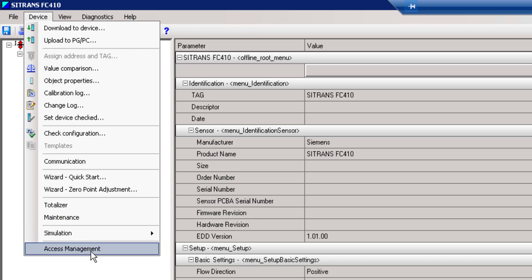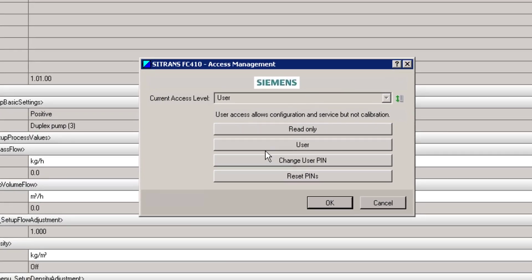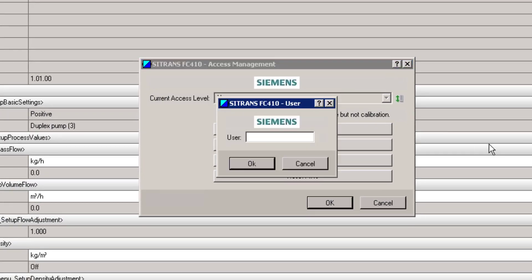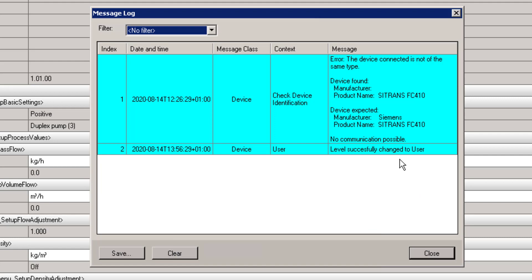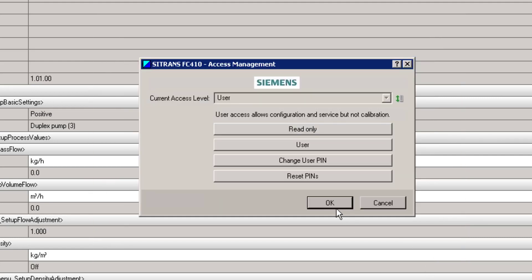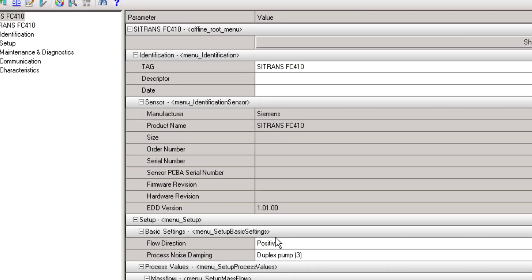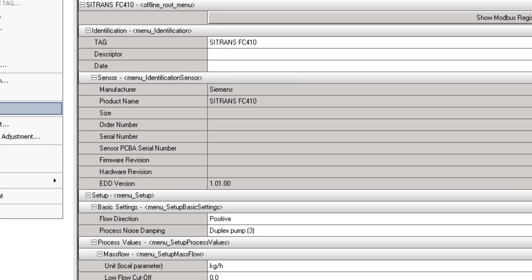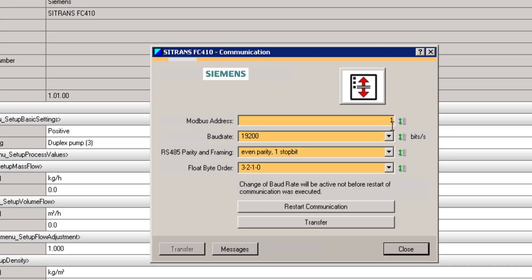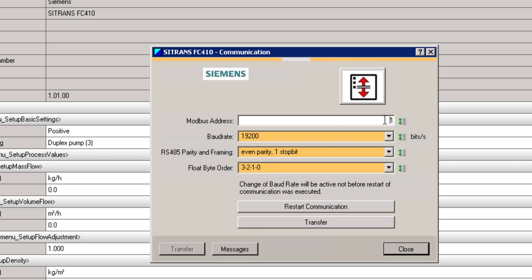So go to user. Type in the user code 2457. Click OK. You can see here, level successfully changed. Now we should be able to go into the communication. Just be careful. If you change your parity and baud rate here, you're going to have to go back to your HMS Anybus device and change it to match. We're just looking at the address of the slave. So I'm going to set that to three. OK. And it should come up with a warning.